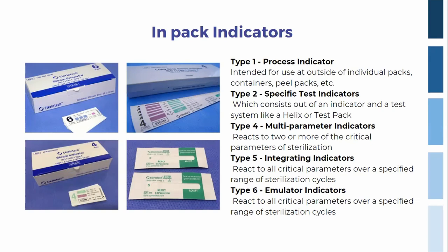The type 4, there's no type 3. The type 4 is a multi-parameter indicator, which reacts to two or more critical parameters of sterilization. And then your type 5, the moving front integrator, reacts to all critical parameters over a specified range of sterilization cycles. Your type 6 emulator indicator reacts to all critical parameters over a specified range of sterilization cycles. So your type 5 and type 6 are the same. However, they test differently. Your type 5 is a moving front integrator, which is not linear, and your type 6 is a linear test.